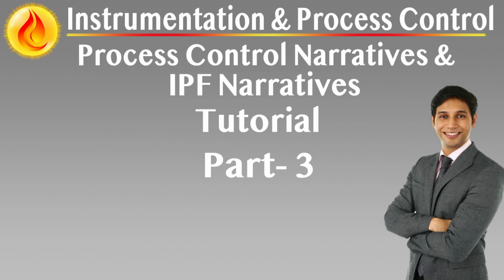Subsystem roles and boundaries identifies each participating subsystem, its control boundaries, and its functional responsibility. Examples include Speedtronic Governor manages turbine load and overspeed protection. CCC controls compressor surge and performance loops. Plant DCS provides sequencing, interlocks, and operator interface. Clear boundaries prevent duplication of functions and misalignment during system integration.